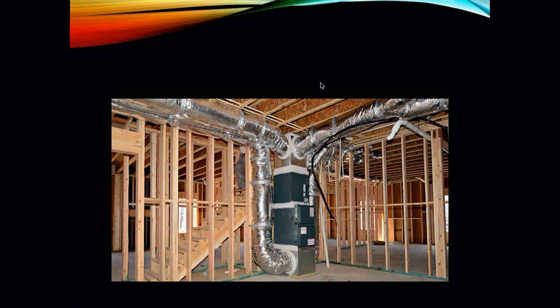Do you see any sags? Do you see any sharp bends? Do you see anything that would possibly really restrict the airflow that is coming out of this particular system? In this picture here, you can also see that the ductwork has been sealed of any leaks, possible air leakage that may be occurring, because we don't want our ductwork to have leaks.